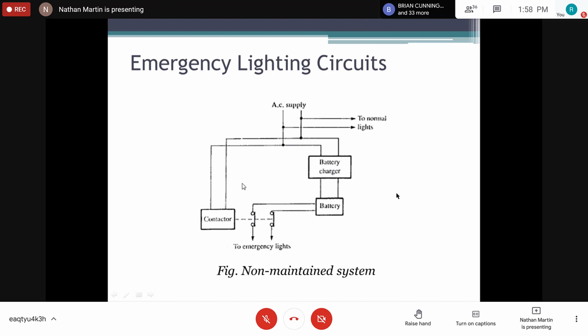If you break it and I don't see any light, it means either the charger is not working, so the battery is not being charged, or the battery itself is defective and is unable to supply the emergency light. So this is the one that we mainly use in emergency lighting. Once JPS goes, the light will come on and light the areas, right?